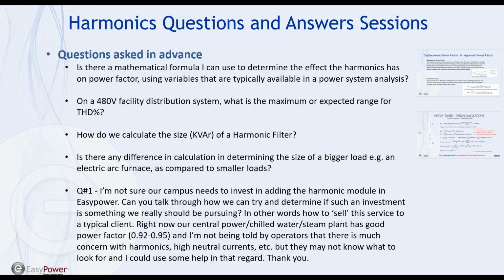And what's important here, I think, to consider is that IEEE 519 does provide a harmonic voltage distortion recommendation of 5%, and it has harmonic current distortion values at the point of common coupling. This standard represents a number. It's not necessarily a number where things fall apart. And it's been my practice, when I do harmonic filter designs and I'm trying to mitigate harmonic distortion, to use 519 as a basis, as a desire to achieve that level or better.